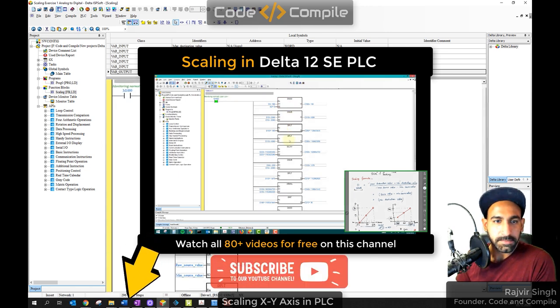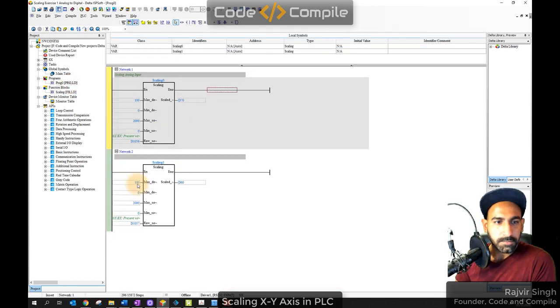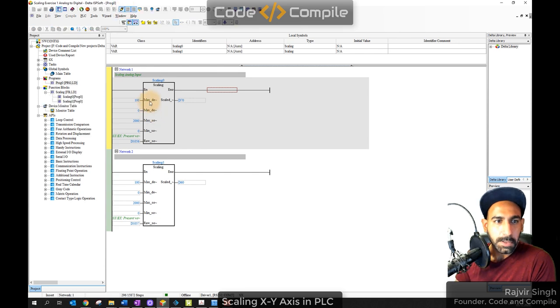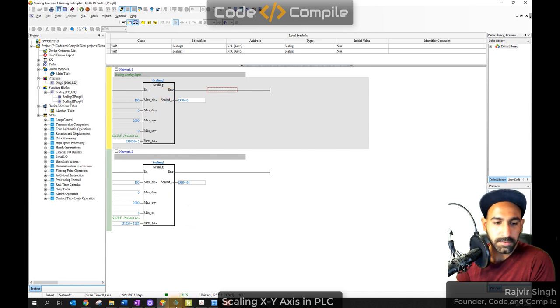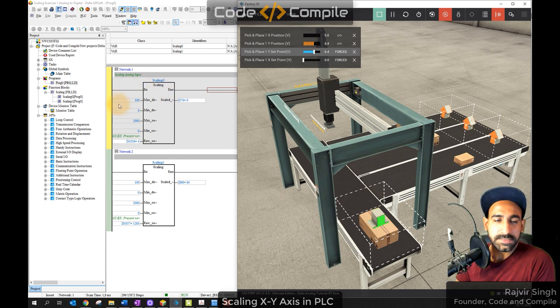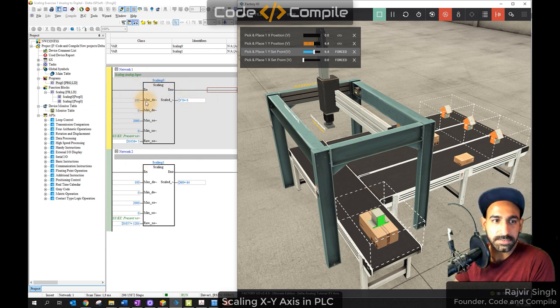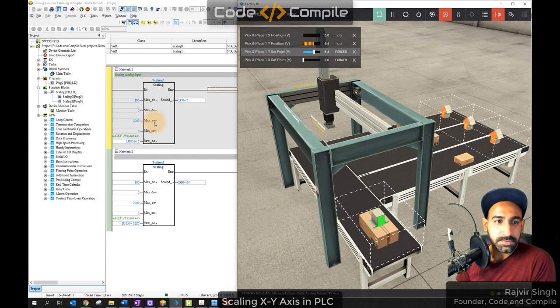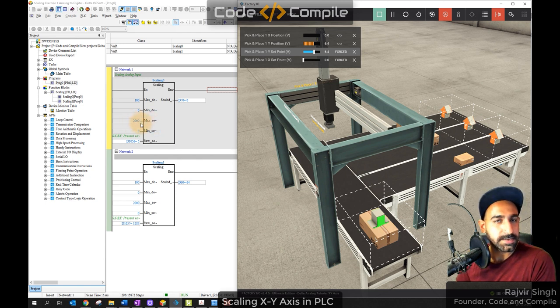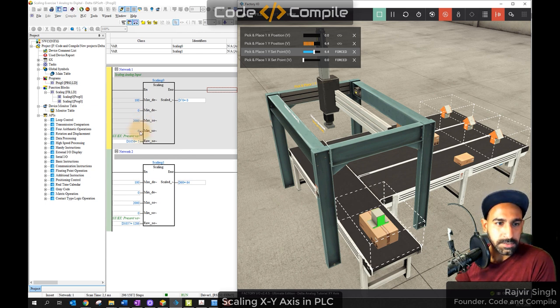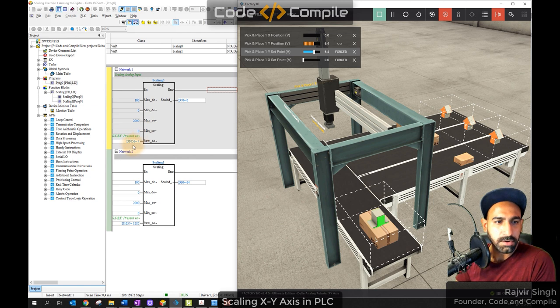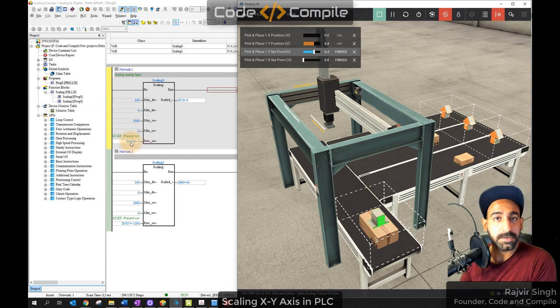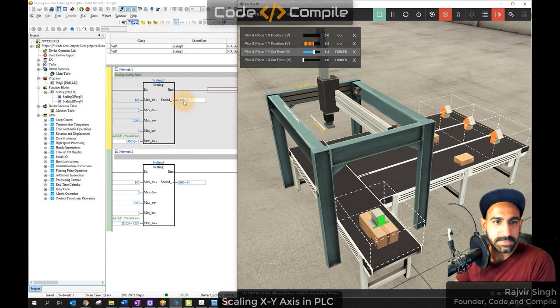So basically I made a function and called it in the program. What do you need to add in the program? It's very simple. Maximum destination value, minimum destination value, maximum source value, minimum source value, raw source value and scaled value. So what do you need to add? Now let's see the maximum destination. I have to read it from 0 to 100%, so maximum percentage is 100, minimum is 0, because I want to read it from 0 to 100%.